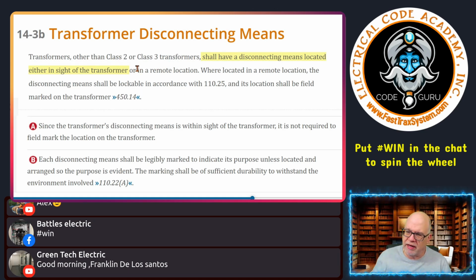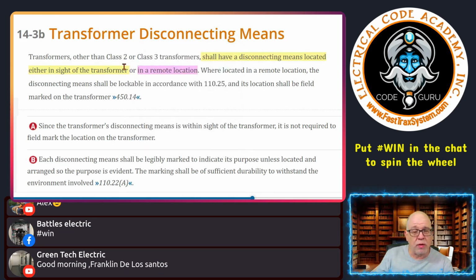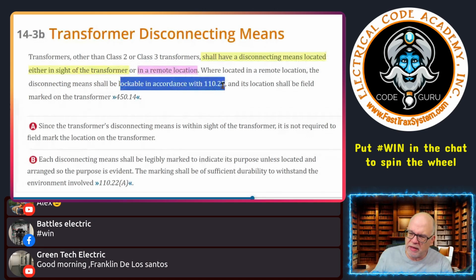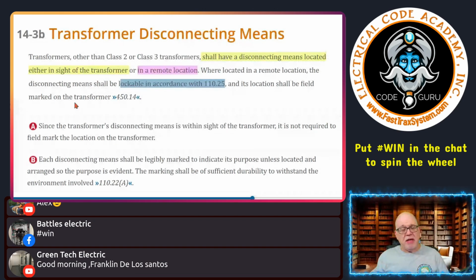It says or in a remote location. Now, when doing so, when located in a remote location, it says the disconnecting means shall be lockable in accordance with 110.25. So what does that mean? That means you have to meet all of the rules, lockable, and all of those requirements in 110.25 have to be met. And there's one other element involved.